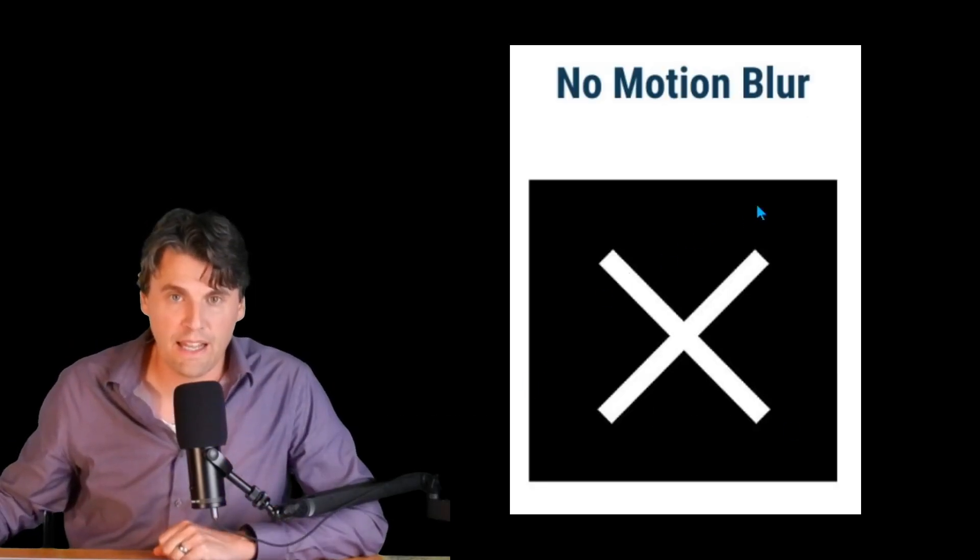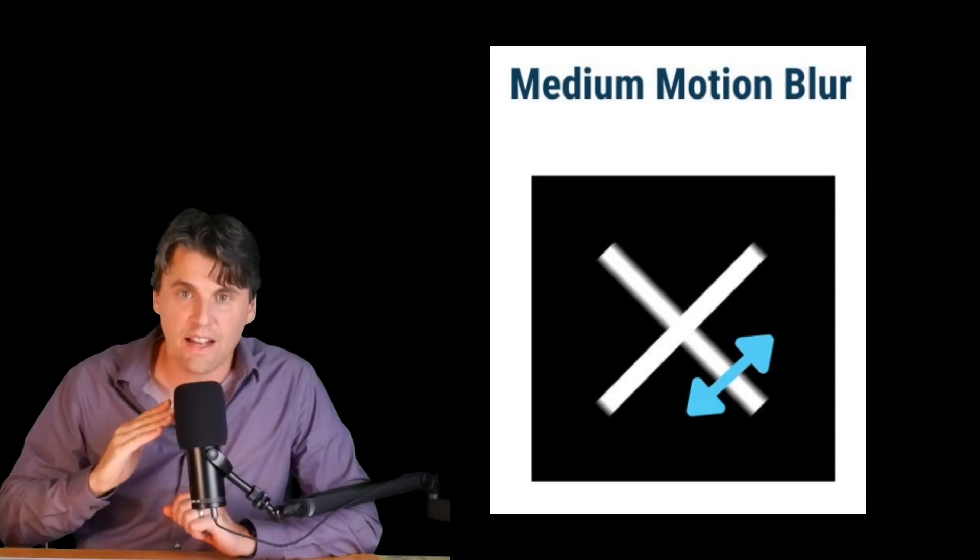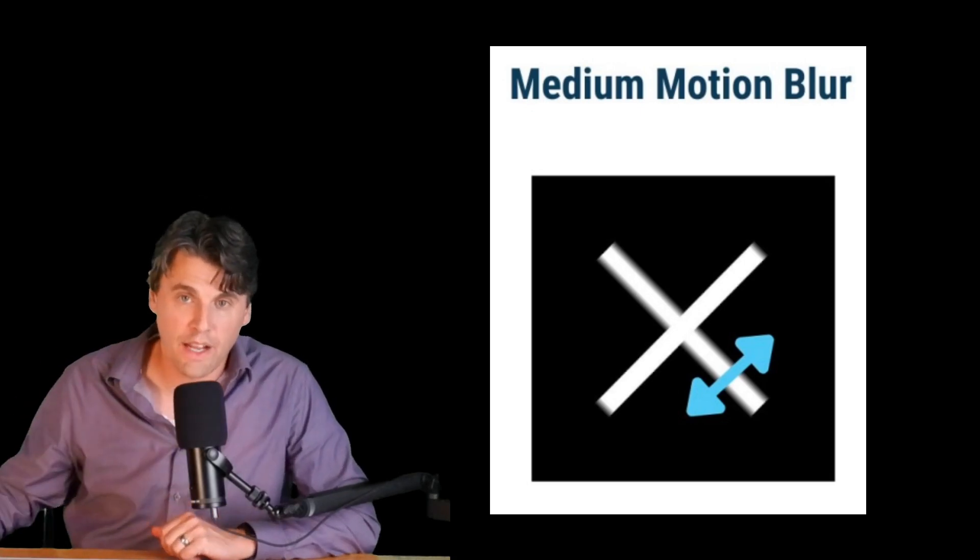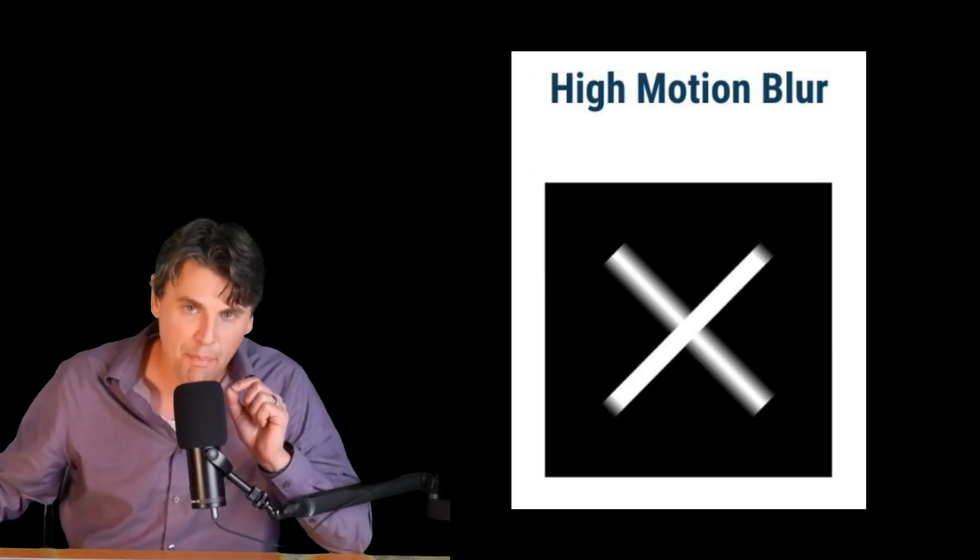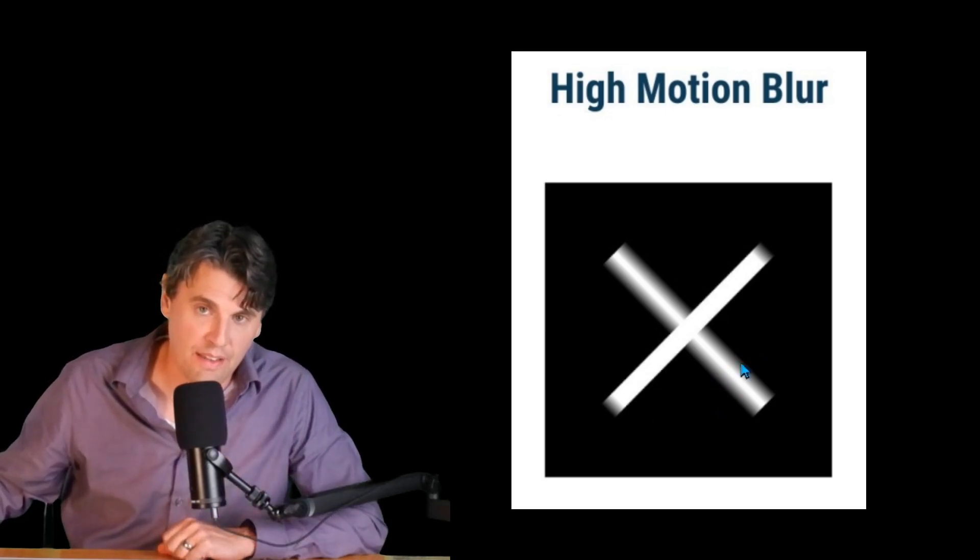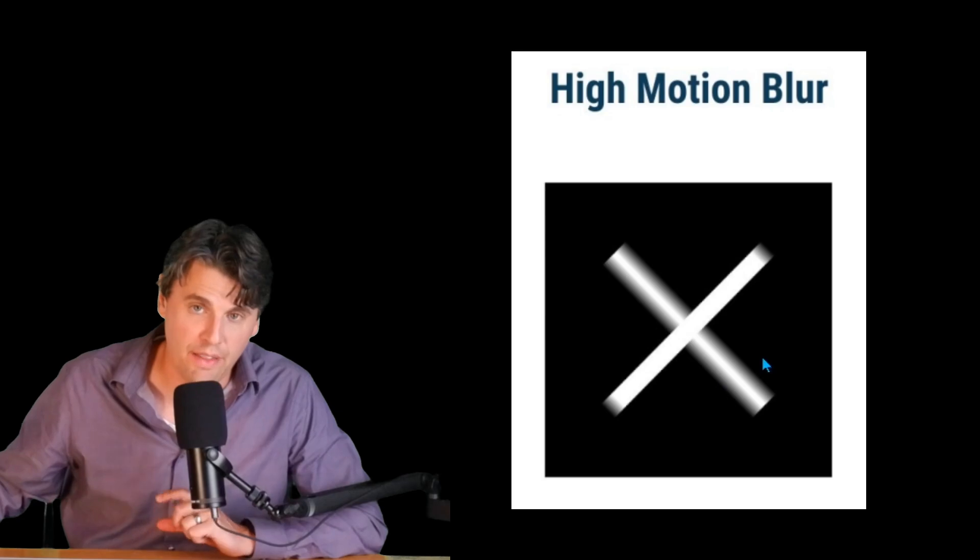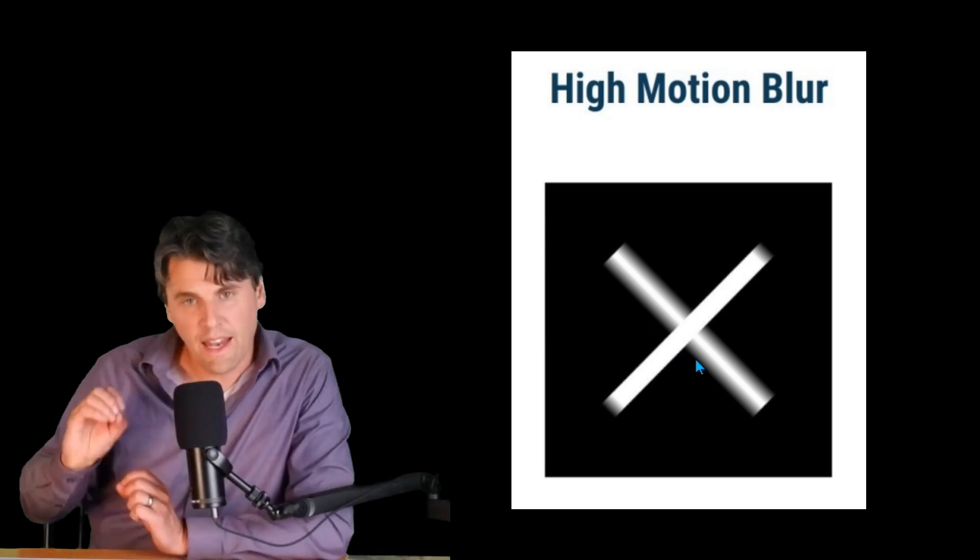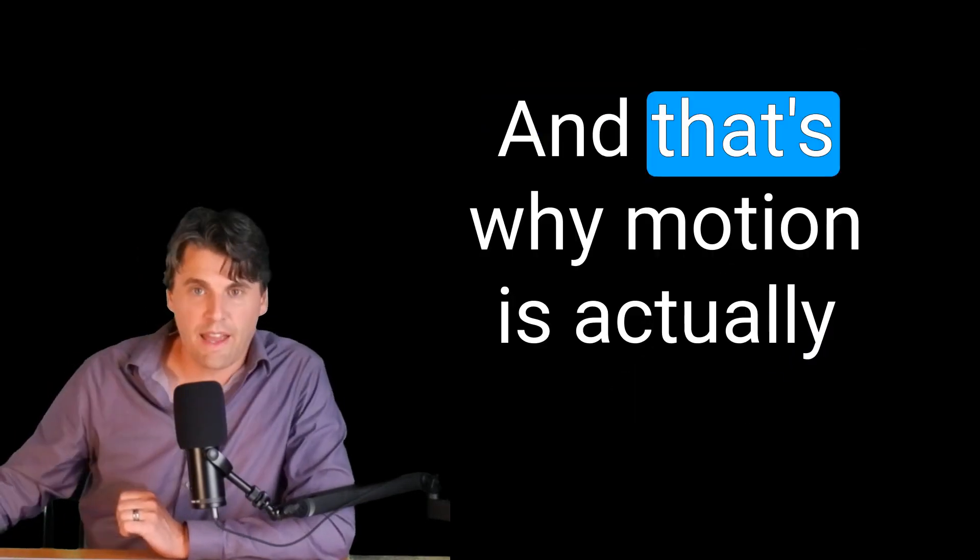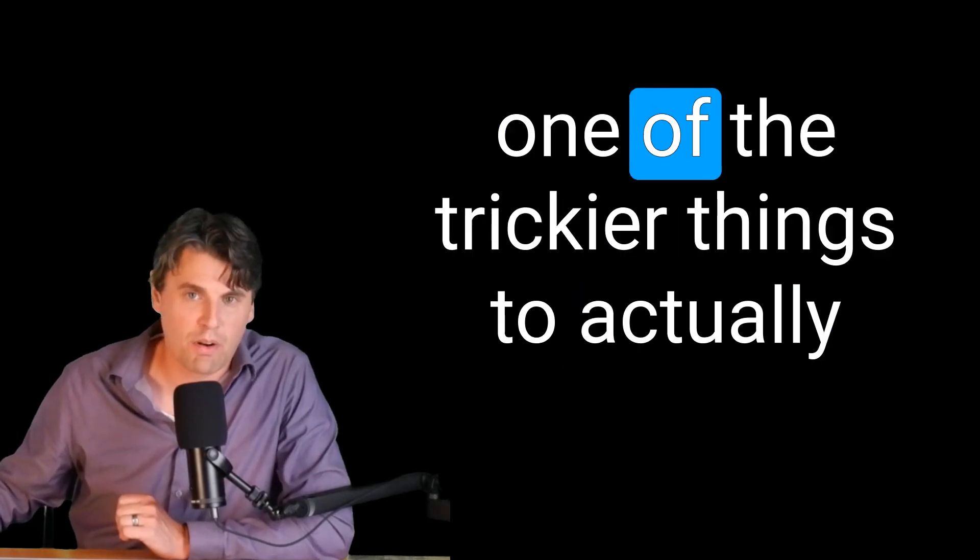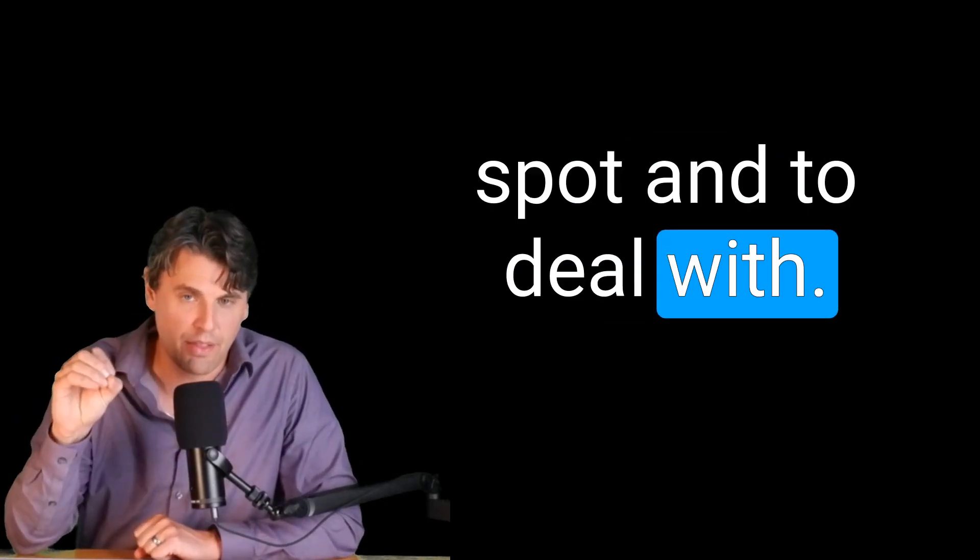If you look again at your X, if you have a nice stationary X, it'll look like this. But if the X is actually moving along an angle, imagine the X is moving along this direction right here, what's going to happen if it moves during the acquisition, is this actually gets blurred. These edges right here are actually getting blurred, because they were moving during the acquisition. However, you can see this edge right here is not blurred. It actually has to do with the direction of the motion. And that's why motion is actually one of the trickier things to actually spot and to deal with.